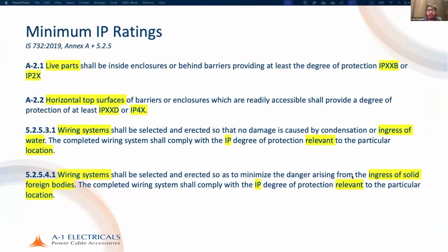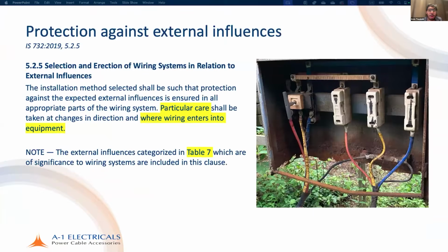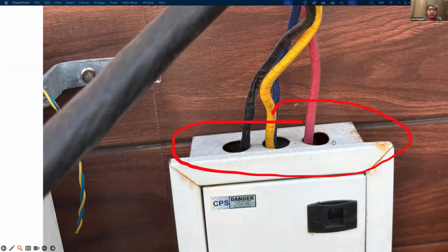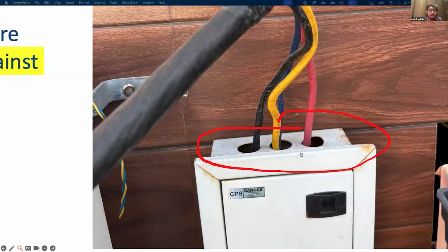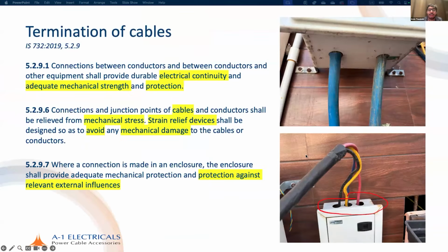And any solid foreign body with a diameter greater than 1 millimeter should not be able to penetrate. Now, clearly, if we go back to our image, you can see that this is far bigger than 1 millimeter. This is a complete violation of the standard. So this is a problem. And these requirements are additional to the requirements that apply for protection against ingress according to the relevant external influences. This is a requirement that applies everywhere.